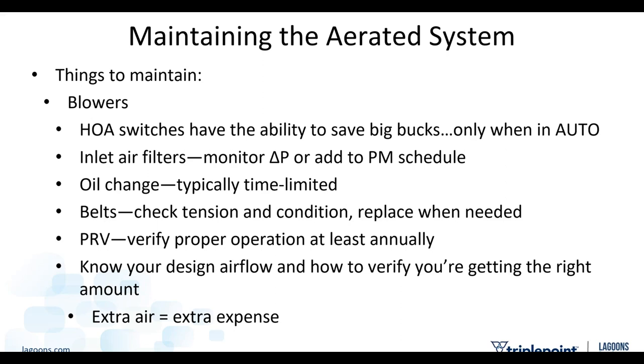That PRV on the back end, the pressure release valve on the back end of the blower, it's important to understand what your set point is. What point should it blow off? Should you be blowing off at 4 PSI? Should you be blowing off at 8 PSI? You should know that and play around with it. Make sure that you verify proper operation. Exercise that valve no less than annually. If you have a manufacturer's recommendation that's more than annually, by all means, follow that manufacturer's recommendation.